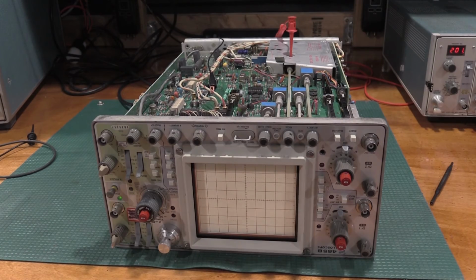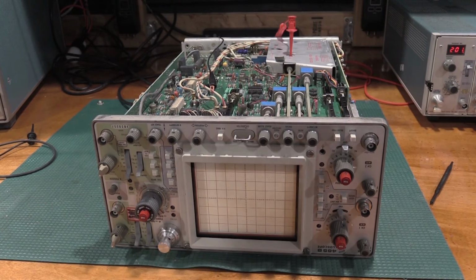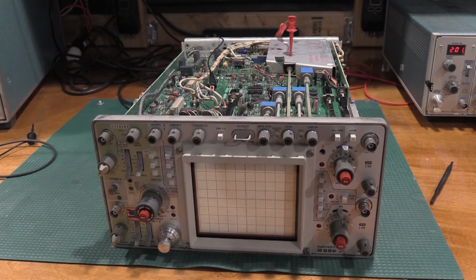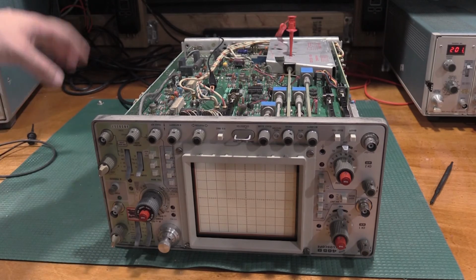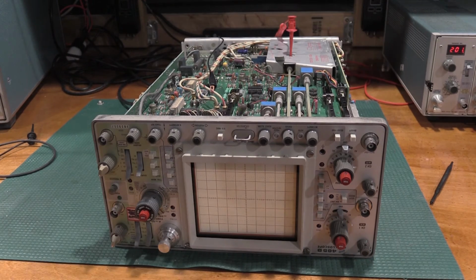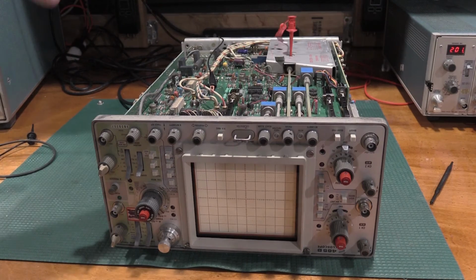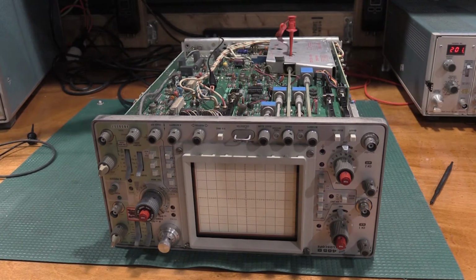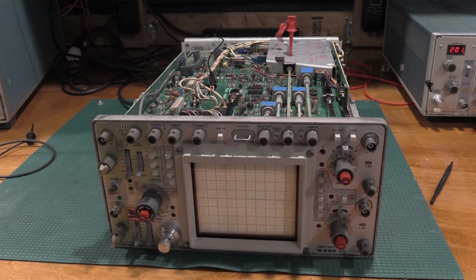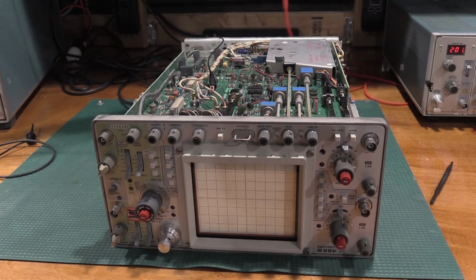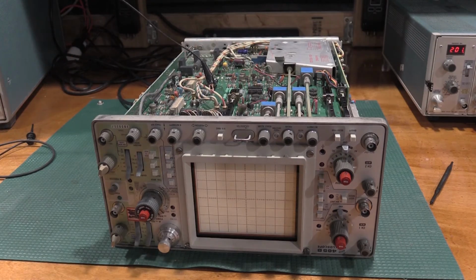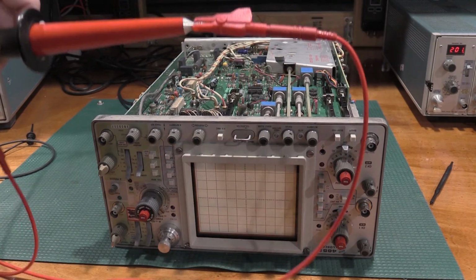Now, just so you guys can see, the scope is on. I'm going to turn that off. Going to unplug it because I don't feel like getting zapped today. And I'm waiting for everything to kind of discharge. The meter's telling me everything is good and discharged. I'm going to give it a little bit more time. Then I'll pull the probe off and pull the ground off and get the high voltage probe out of here. Okay, that should be enough time. Just pop this off. And here was my test setup.